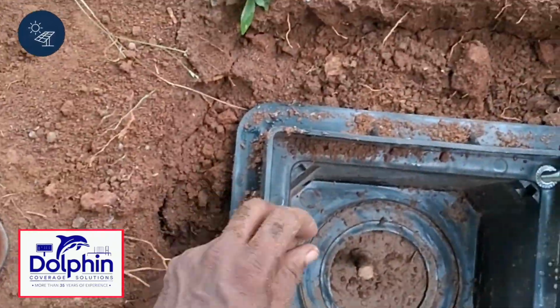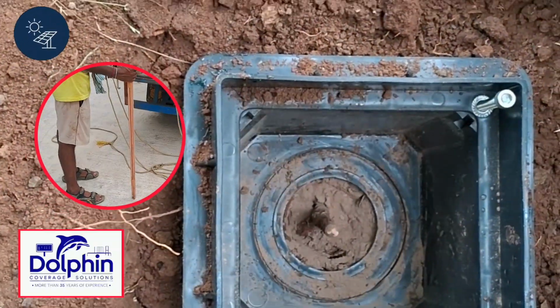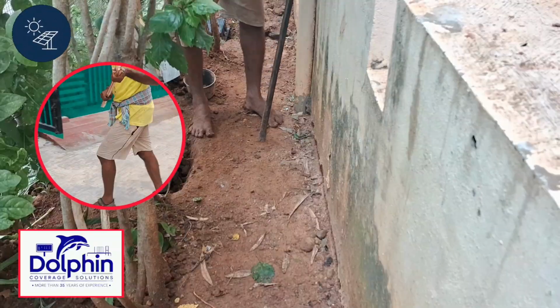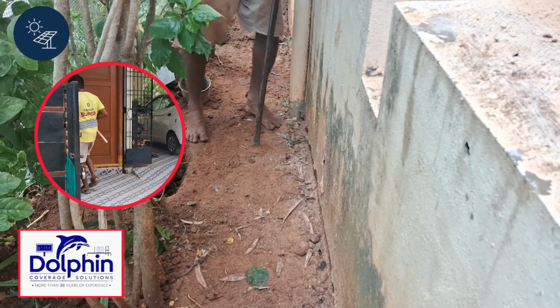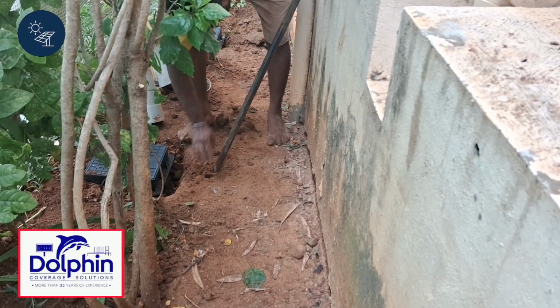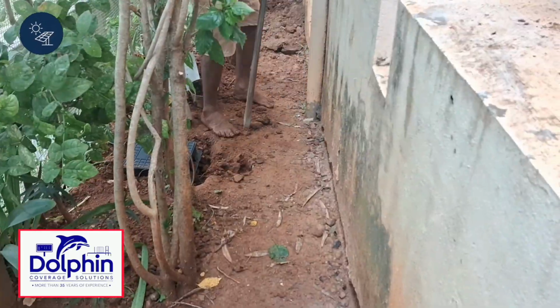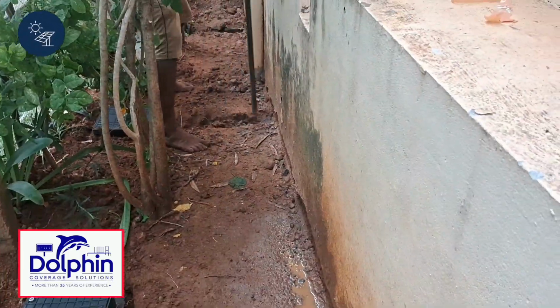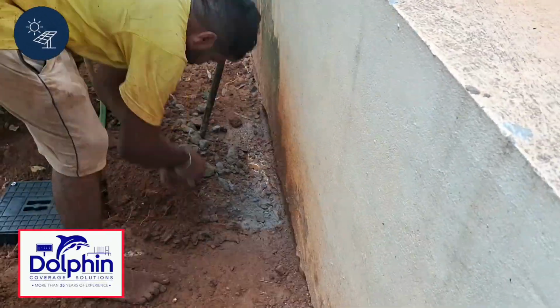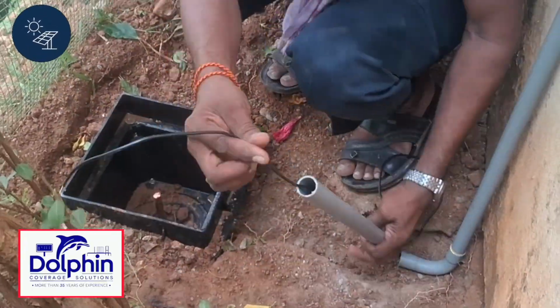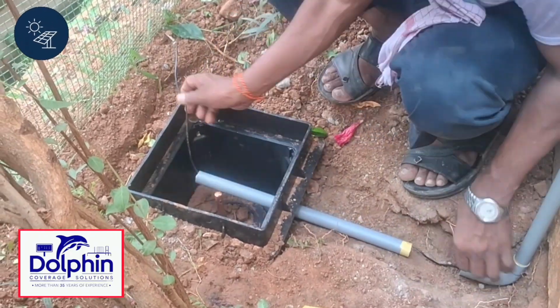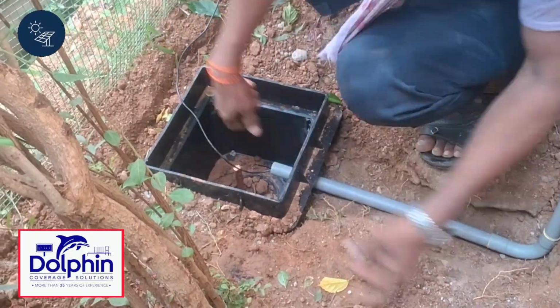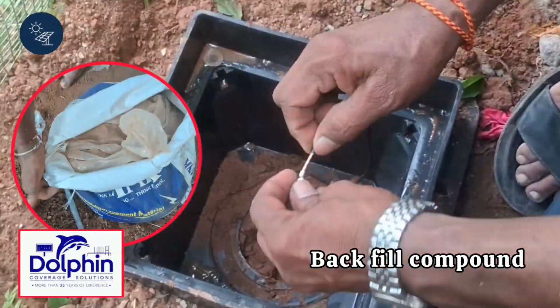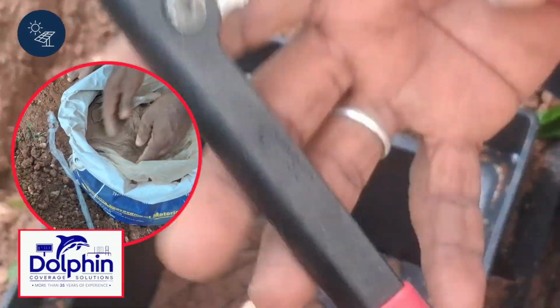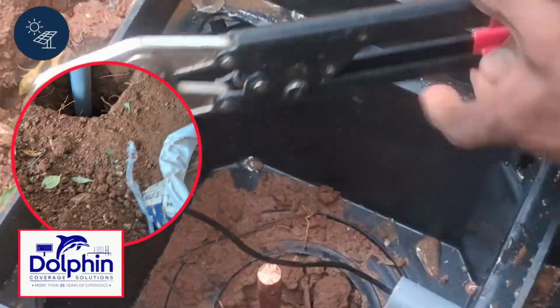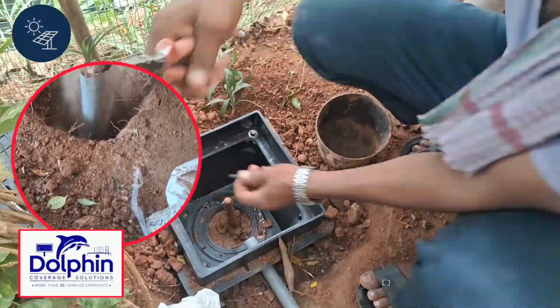Earthing electrodes. Choice of material. Copper is generally preferred due to its low resistivity and corrosion resistance. Though galvanized iron is also used, copper is more expensive but offers better performance. Pipe earthing, commonly used, involves burying galvanized steel or copper pipes deep into the ground. Plate earthing: copper or GI plates buried deep into the soil to prevent static charges and stray currents. Chemical earthing utilizes chemical compounds like bentonite or backfill compound around the electrode to reduce soil resistance and improve conductivity. This is highly recommended for long lasting performance.